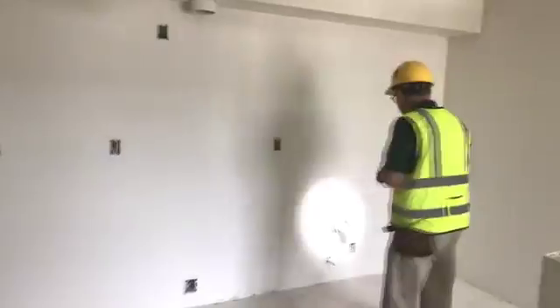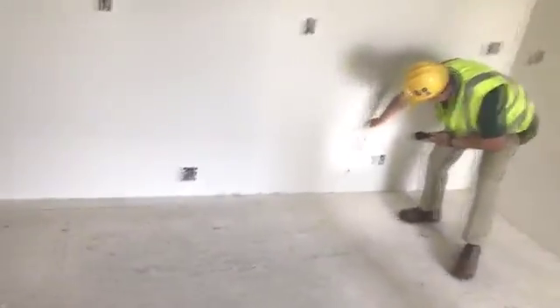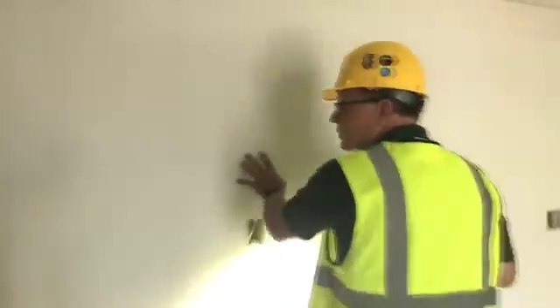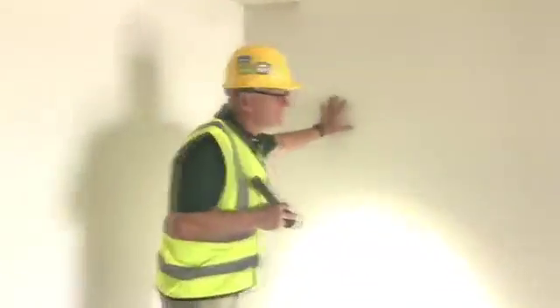Okay, this has a little island in here. Again, they need to get in here and do their caulking before we come and do the blower door test to see how the infiltration rate is. They haven't quite got that far. And this is an interior wall right here. This is an interior wall to the corridor, and this is a common wall to the unit next door. We also have in this area a bathroom. Again, compartmentalization, that stuff must absolutely be sealed. We haven't gotten to that for our test yet.